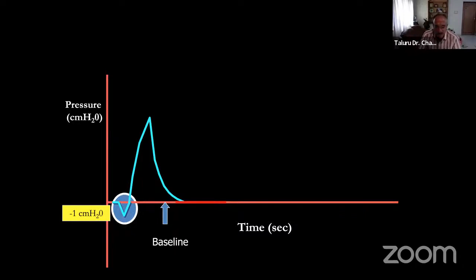See, I've set a trigger of -1 centimeter. If the patient has an auto PEEP of 5, now how much should the patient be able to produce negative pressure to come to -1? How much negative pressure he has to generate to trigger? See, the baseline is here, baseline is here. The ventilator doesn't have the information that auto PEEP is being generated. Now the baseline shifts here, but it has to again touch this point to trigger a breath. So how many centimeters of negative pressure does it have to generate?